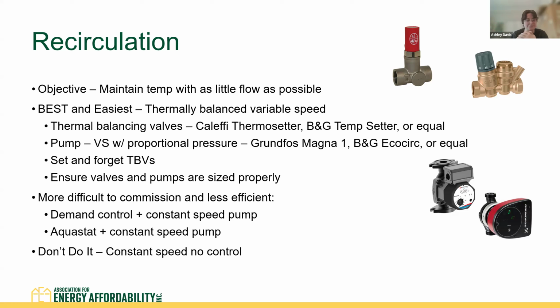Right? If you're using a different type of balancing valve, you might have to go through the whole building and pressure balance them. And then demand controls and aquastats rely on temperatures of the return. And if you've got multiple loops, those pumps might turn off even when a longer loop isn't fully heated. You should pretty much never be doing a constant speed pump that has no controls when doing a central heat pump water heating system. Next slide.